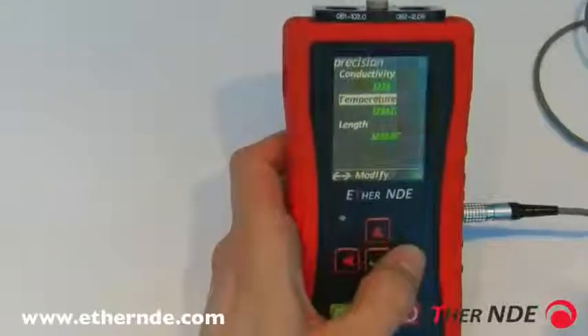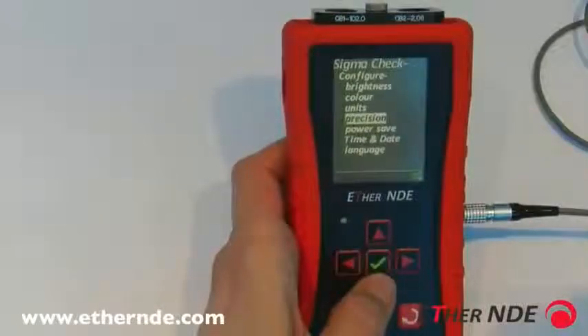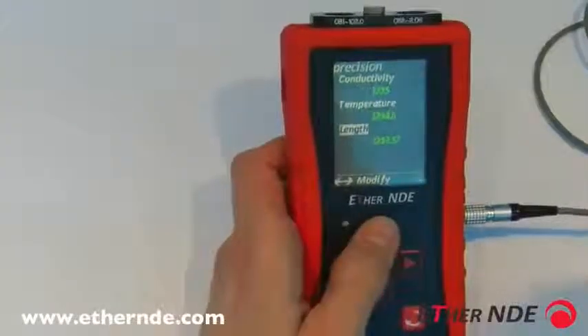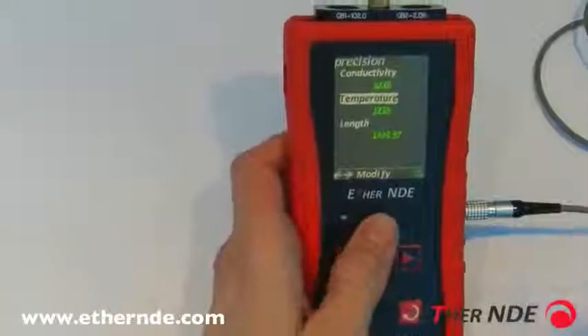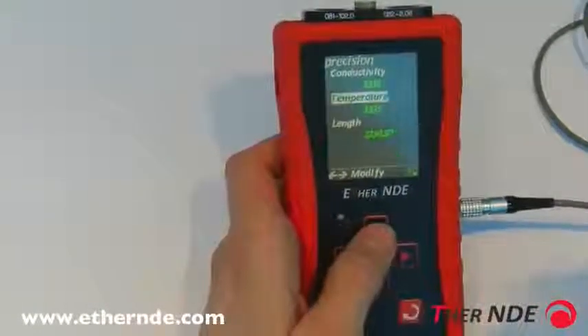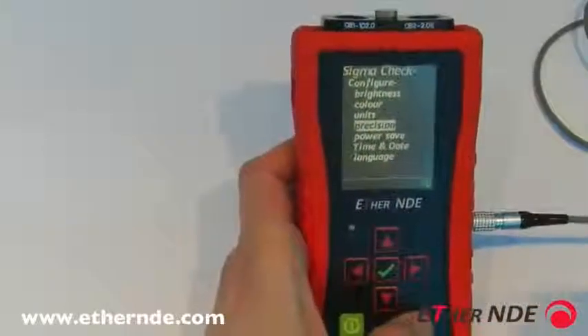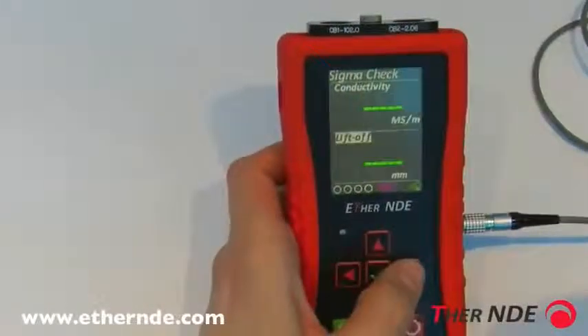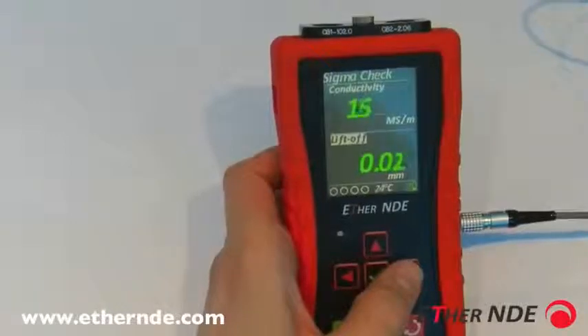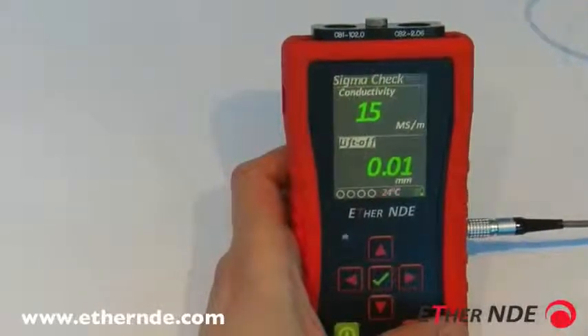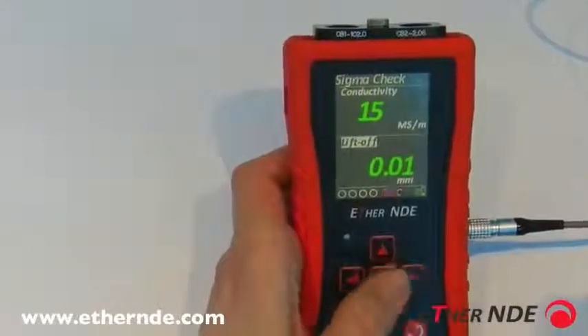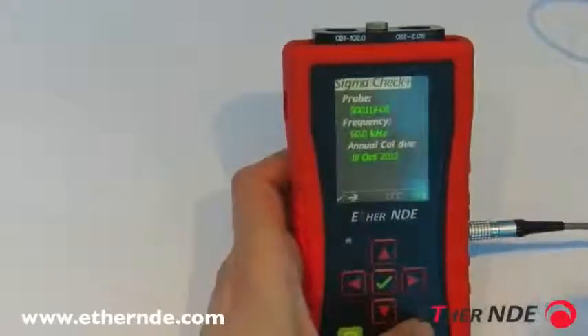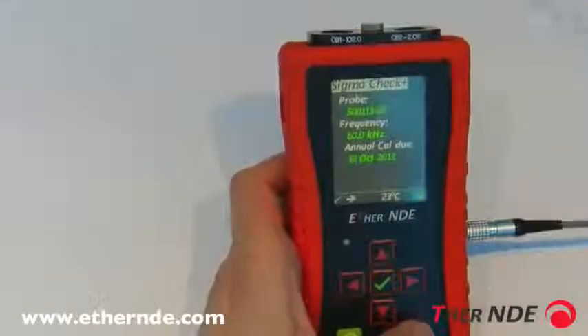For temperature you can have zero or one decimal point; for length, zero, one, or two decimal points. To demonstrate: with temperature set to none, conductivity to none, and length to two, pressing tick to accept and going to the reading screen with liftoff displayed, you can see no decimal points on the conductivity and two decimal points on the liftoff. The temperature at the bottom also shows zero decimal points. That explains the precision menu item.